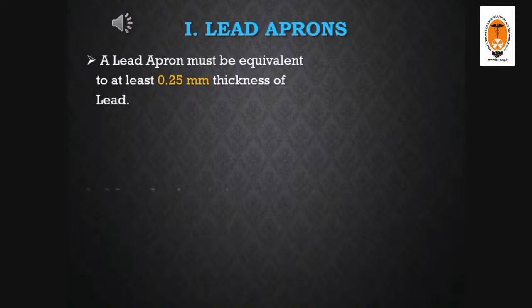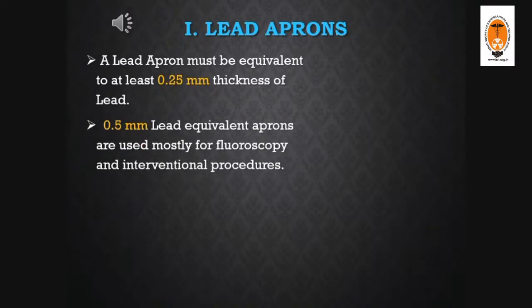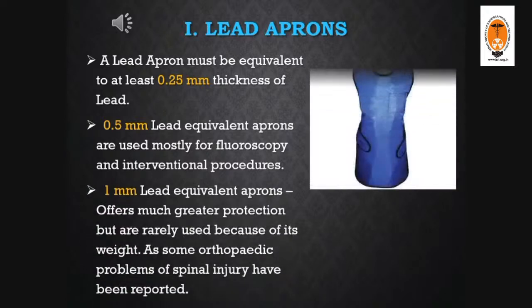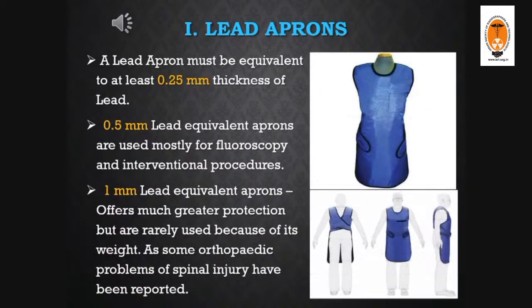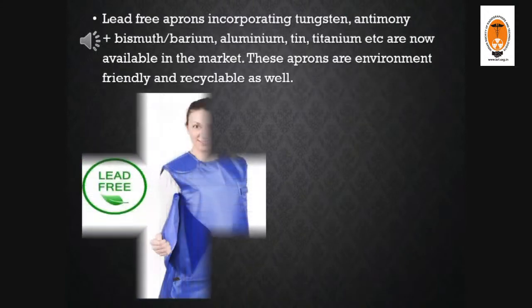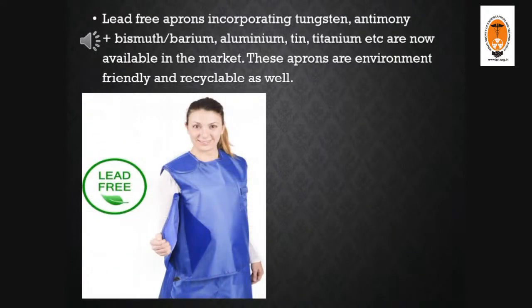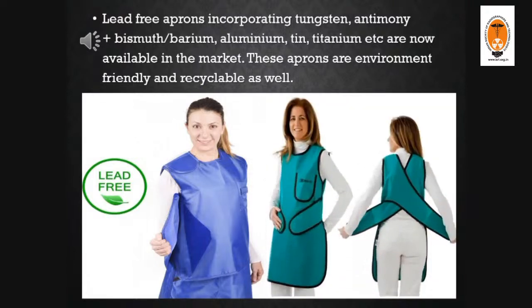A lead apron must have a lead equivalence of 0.25 mm thickness of lead, or 0.5 mm is used in fluoroscopy or interventional procedures where there are long durations of exposure. There are also 1 mm lead equivalent aprons available, but they are barely used because of their heavy weight, which could cause spinal injuries, etc. A solution to the problem of heavy weight of lead aprons is the availability of lead-free aprons. These are made using tungsten or antimony or bismuth, aluminium, tin, titanium, etc.